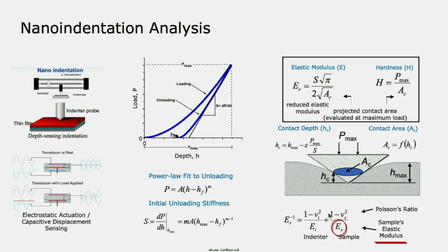We are using a very high accuracy transducer, and this transducer can record the applied force and the displacement during the indentation procedure. So this is the diamond probe. The diamond probe has a known shape, and we can apply the force with our transducer, indent into the material and pull out from the material. During the indentation procedure, we get the displacement and load curve from the transducer. And this gives us some good information about the mechanical properties.